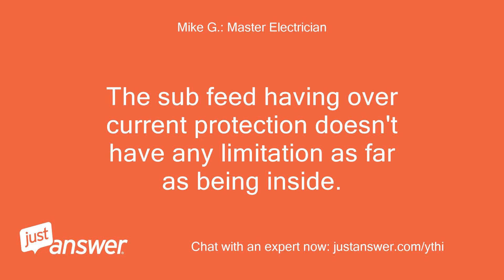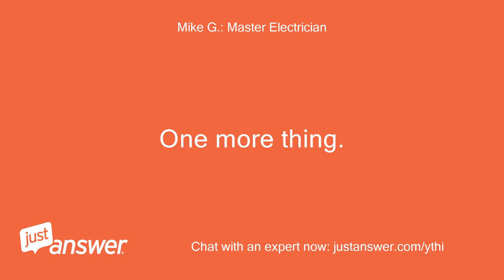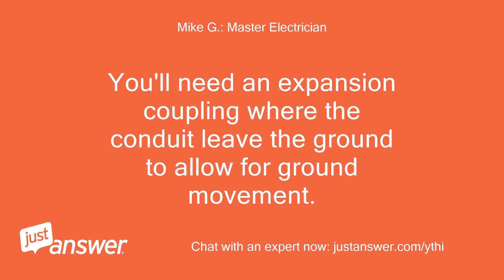The sub feed having over-current protection doesn't have any limitation as far as being inside. Using URD cable will require conduit box-to-box. You'll also need an expansion coupling where the conduit leaves the ground to allow for ground movement.